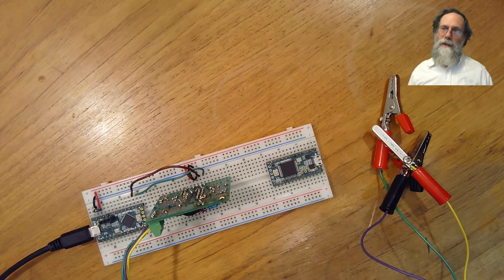When we're talking about EKGs, the term lead really means channel. And so it doesn't refer to the number of wires, it refers to the number of distinct differential channels that are being recorded. So a 12-lead EKG, which is the standard one used by cardiologists for diagnosis, doesn't have 12 wires. It's got 12 channels. In fact, it's got 10 wires.